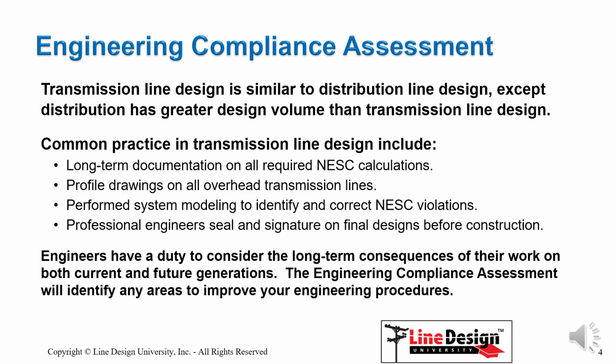Distribution line design closely resembles transmission line design, except for the large disparity in the number of designs. Transmission companies made major advances during the last 25 years by incorporating engineering software that performs and provides long-term documentation on required NESC calculations, profile drawings on all overhead spans, system modeling to identify and correct all NESC violations, and affixing the professional engineer's seal and signature on final designs.